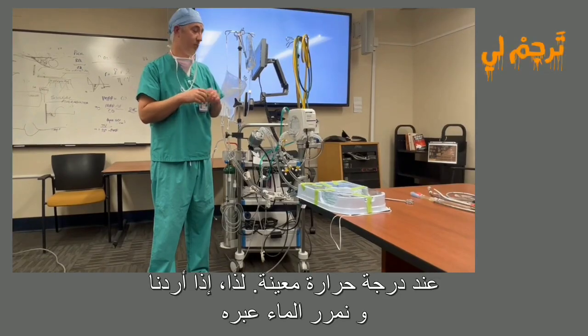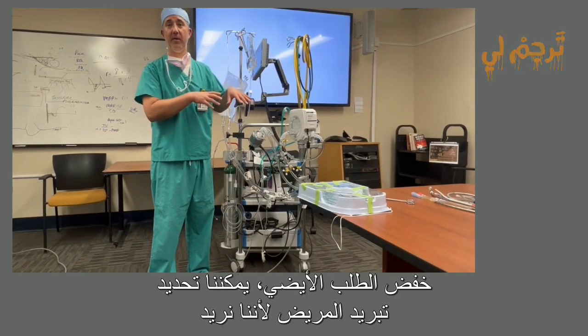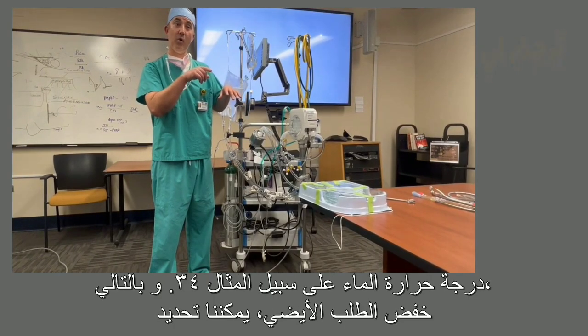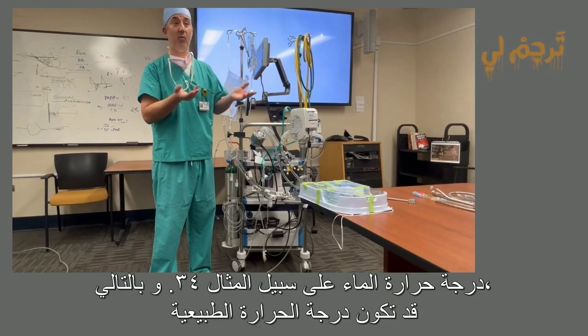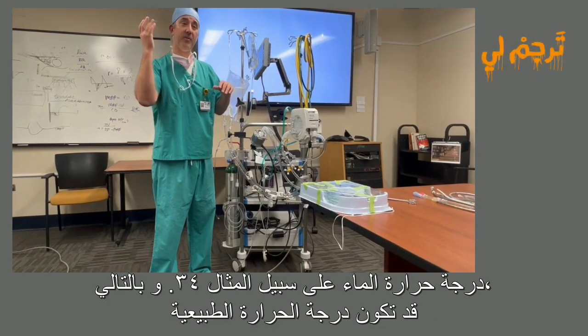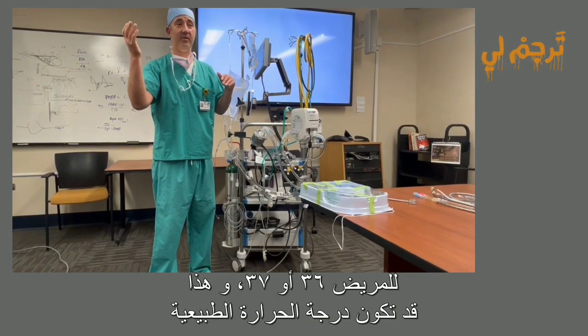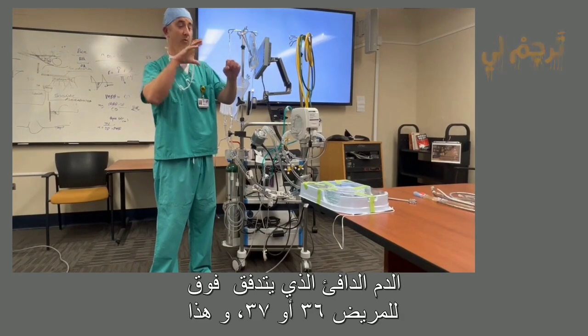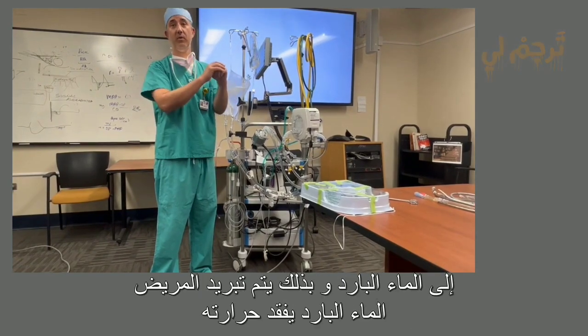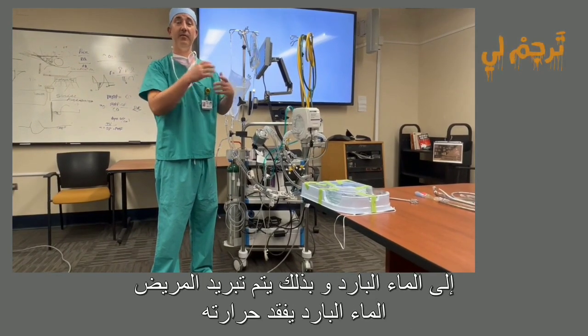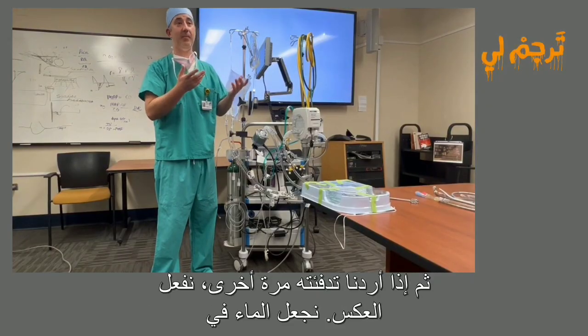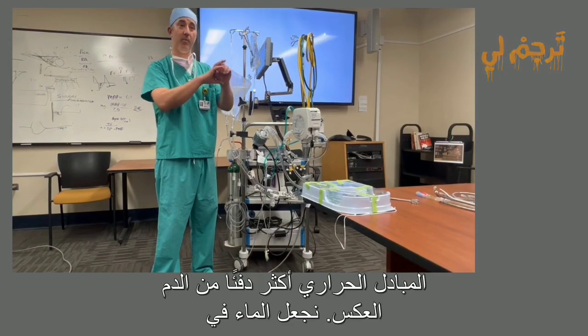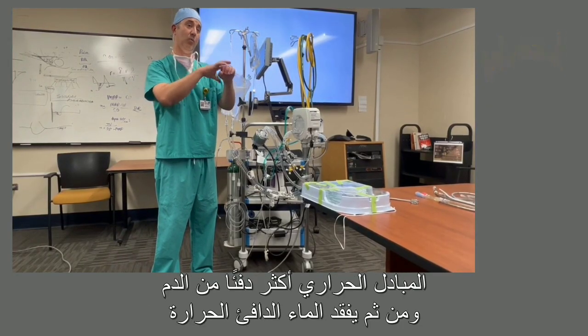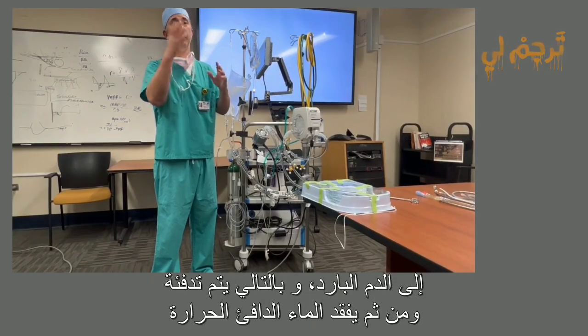So if we want to cool the patient because we want to lower the metabolic demand, we can set the water temperature to, let's just say, 34. So the normal temperature of the patient might be 36 or 37, and that warm blood that's running over the cold water loses heat to the cold water, and you cool the patient. And then if you want to warm them back up, you do the opposite. You make the water in the heat exchanger warmer than the blood, and then the warm water loses heat to the colder blood, and you warm up the patient.